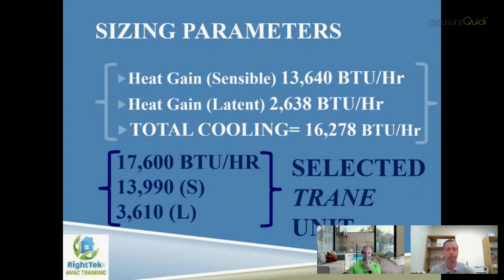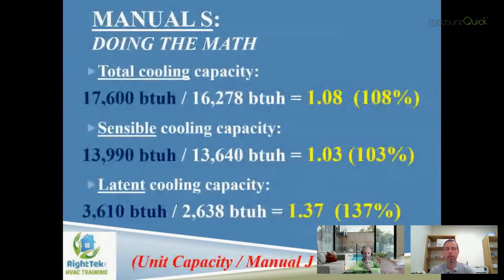Then all I have to do is apply the procedure that Manual S gives us. Down at the bottom in red, it's pretty straightforward. You take the capacity of the unit and divide it by the respective heat gain from Manual J. So if you go down the line here, you'll see at the top our total cooling capacity for that system was 17,600, and I've divided by my total cooling load of 16,278. And what you're seeing, in simplified wording, is that we're oversized by about 8%. So this system has about 8% excess cooling capacity on the total cooling load side, which is really what Manual S is set up to focus on. But I like to look at a little bit more.